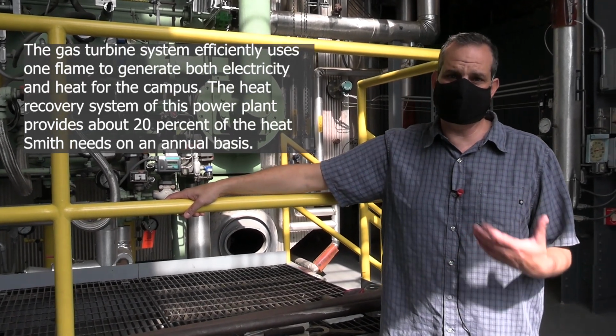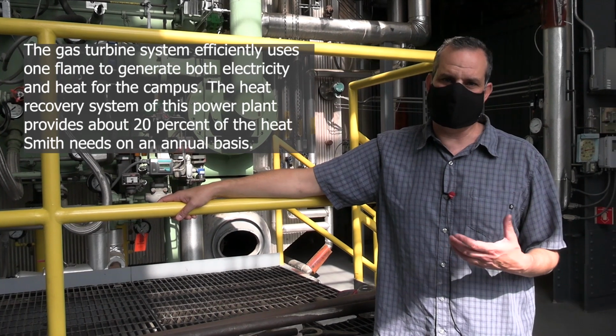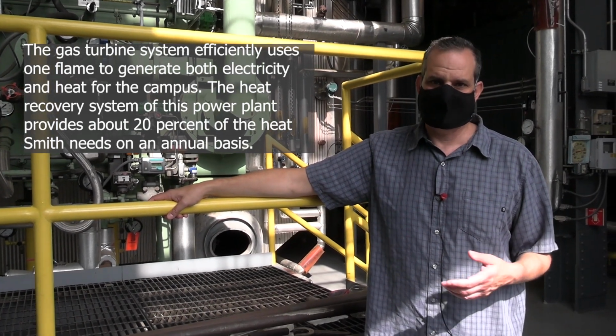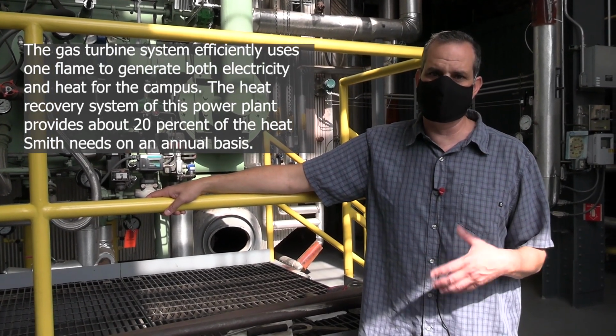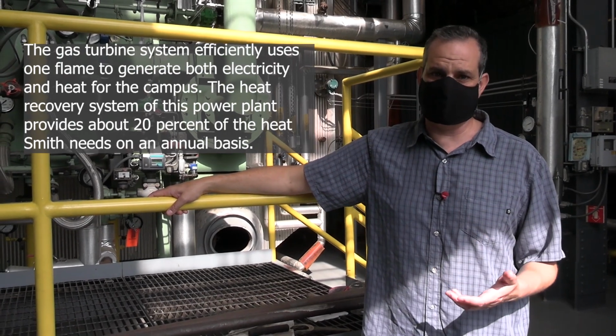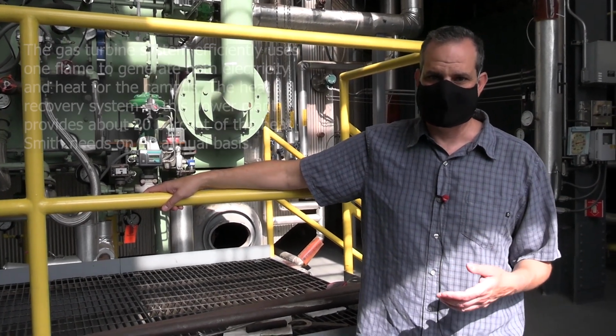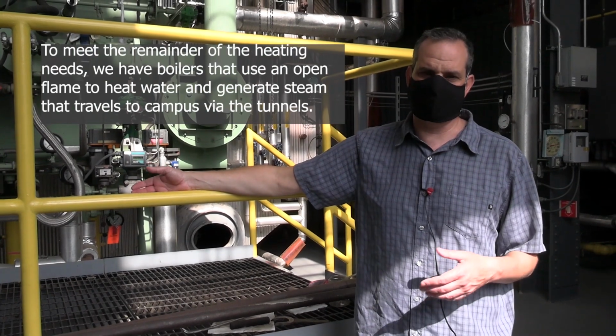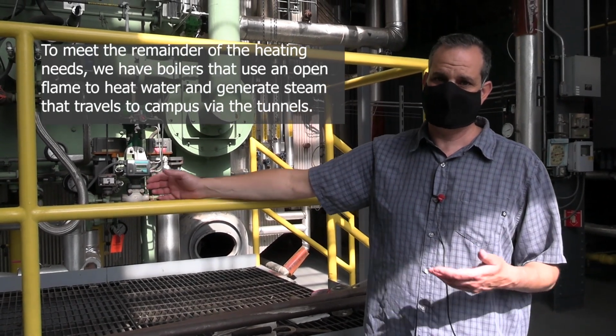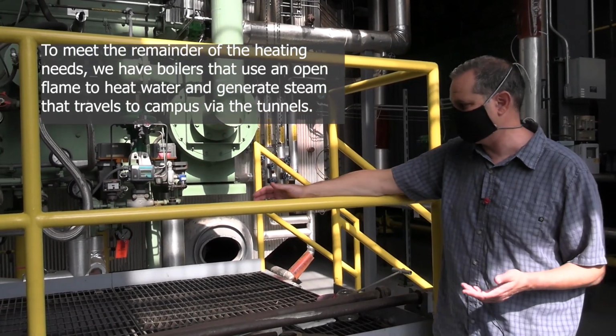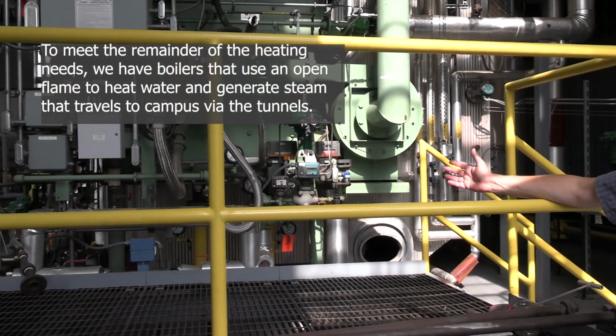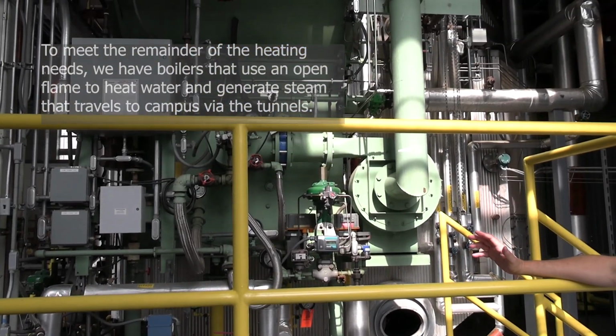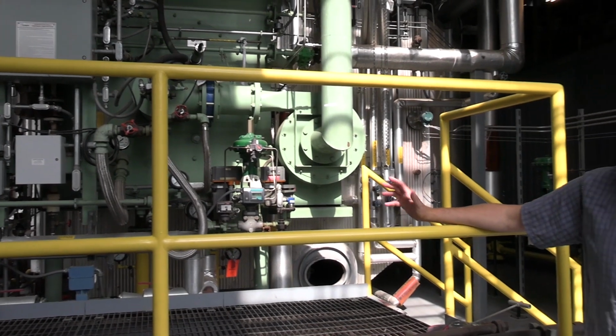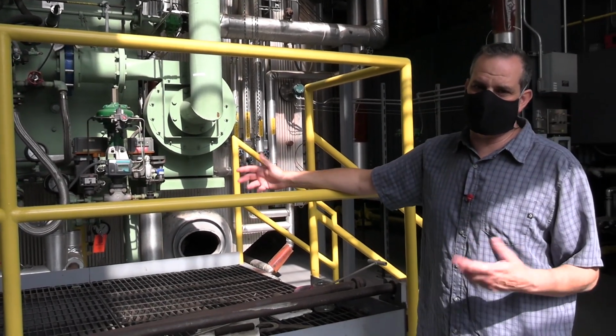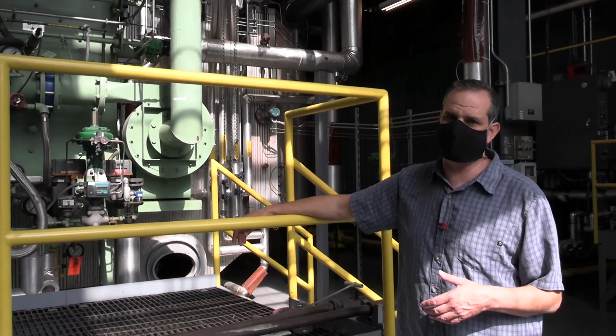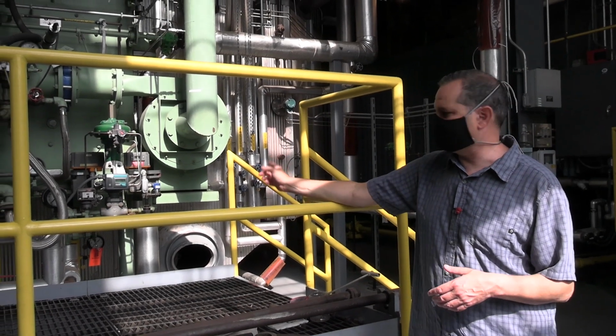On the coldest day, it's maybe providing about a third of the heat we need. So over the course of a year, we need more heat than the heat recovery system can provide. So we have boilers — sometimes called peaking boilers — but essentially they do the same thing: a series of pipes with an open flame heating up the water in those pipes, turning it to steam.